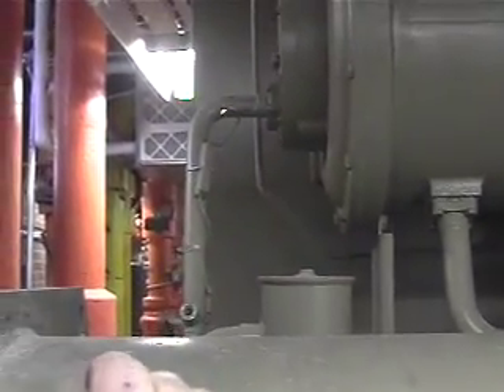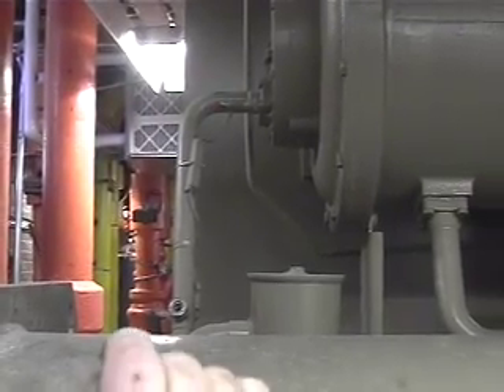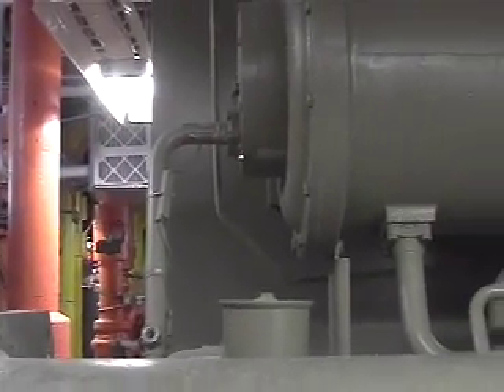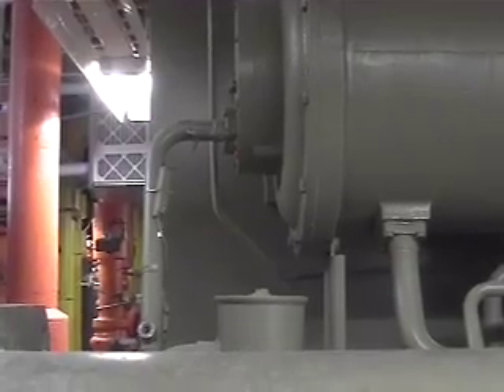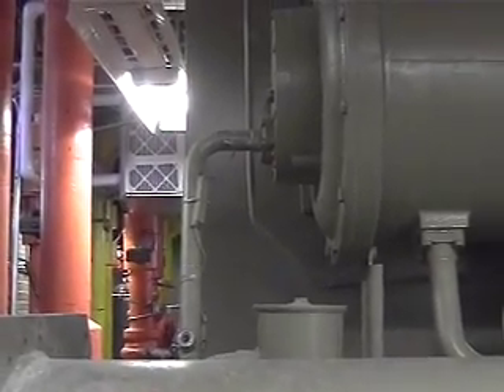This little line with the 4 bolts on it, there and there, is your refrigerant return. This line right here, that's your oil return. As the oil goes over the bearings, it goes down into the bottom of this plate and down into this line, which returns back into your oil sump. The same thing on the front bearing. There's your other line on the front bearing.